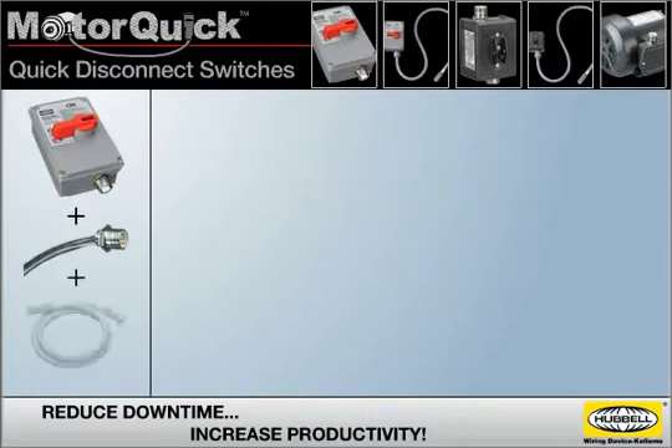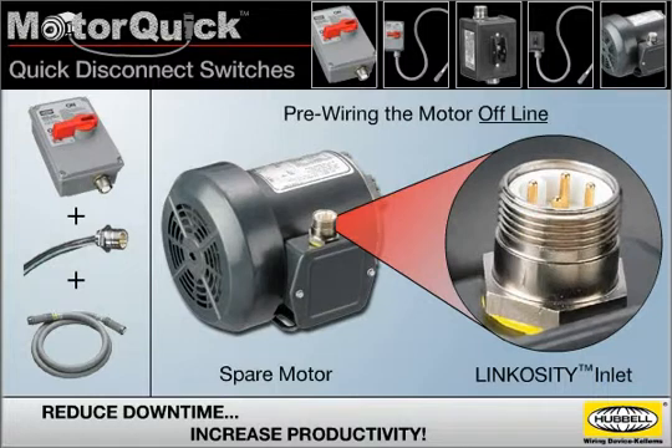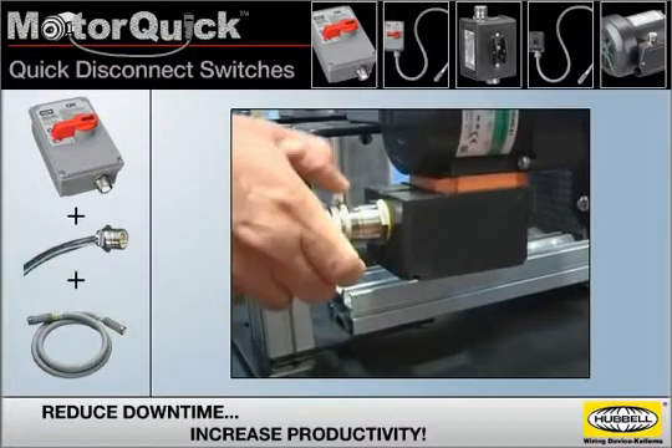Taking advantage of MotorQuick Quick Disconnect switches simply requires pre-wiring a Linkosity inlet to the junction box of a spare motor. This prep work can be done when it's convenient rather than when it becomes critical. By pre-wiring the motor offline, proper wiring can be ensured prior to installation. When a motor change-out becomes necessary, most of the work will already be done, minimizing downtime.